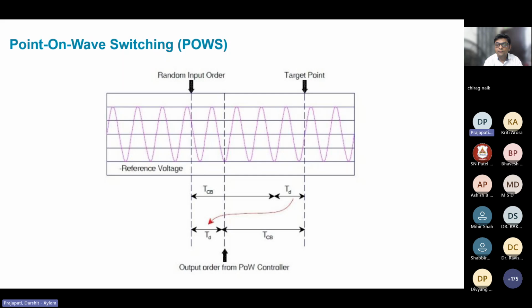So, point on wave switching. This is the concept implemented as a preventive and prescriptive maintenance technical approach for dealing with the operation of the breakers. So the solution to this problem is this. Point on wave switching carefully controls the voltage and current waveforms during switching operations by synchronizing the breaker operations with the voltage waveform. It minimizes the pre-strike and restrike arc, reduces the transient overvoltage, and significantly protects the contacts from erosion.